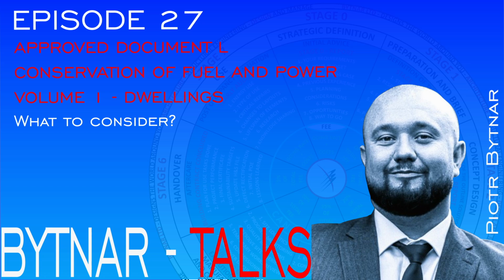In the gist, fixed building services need to be commissioned to assure the operation is good and proper. This involves the formation of a commissioning plan that identifies what is being tested and how, and what does not require testing and why. It forms part of your submission to building control.